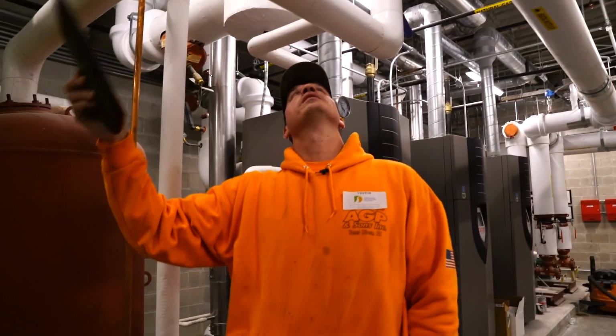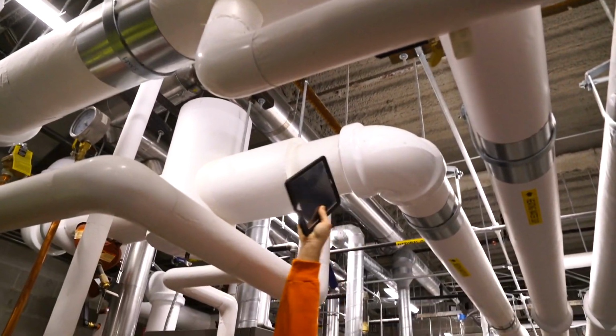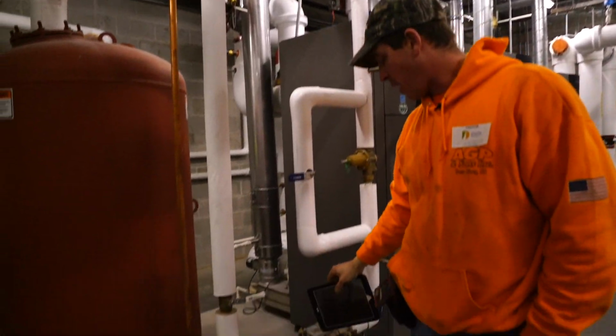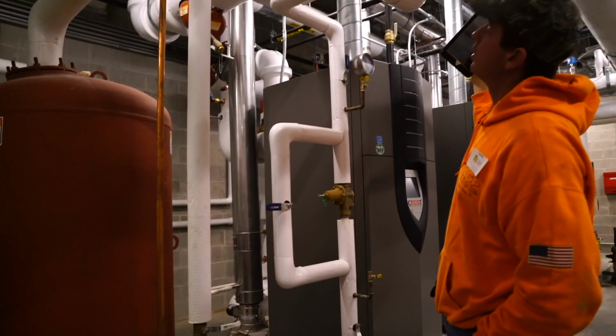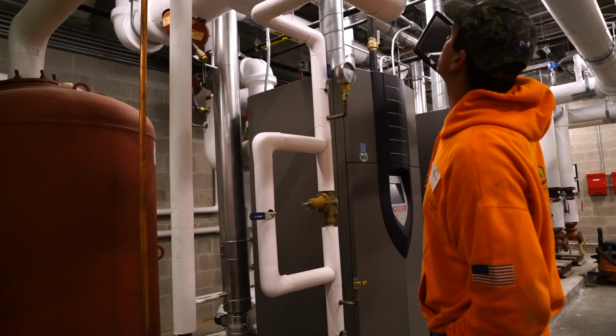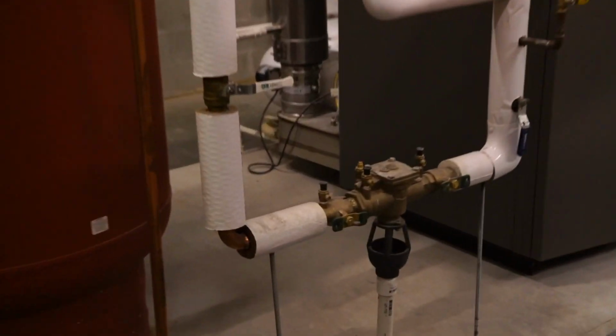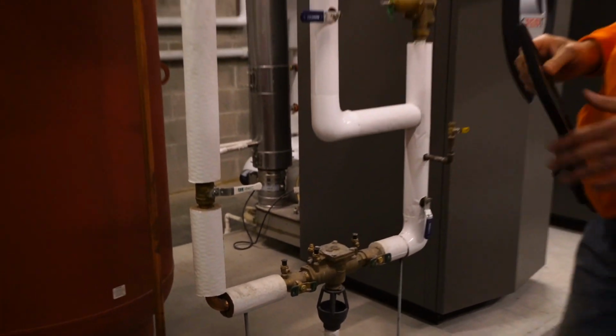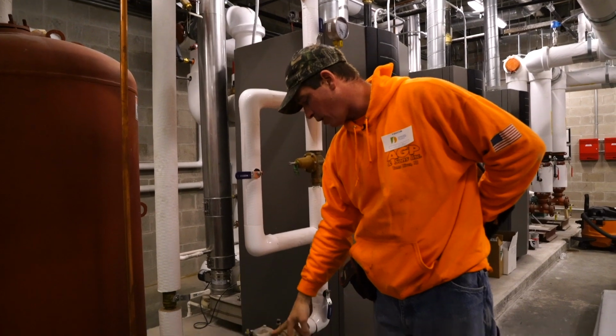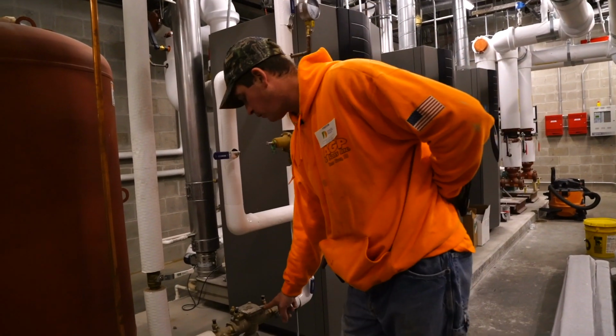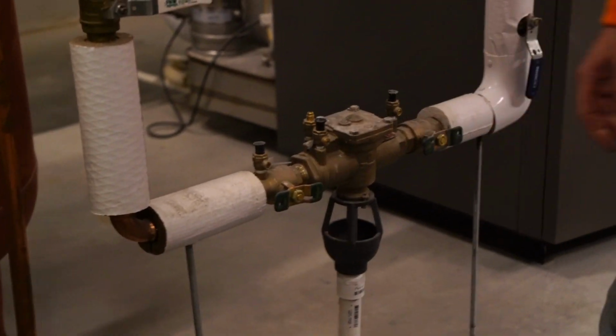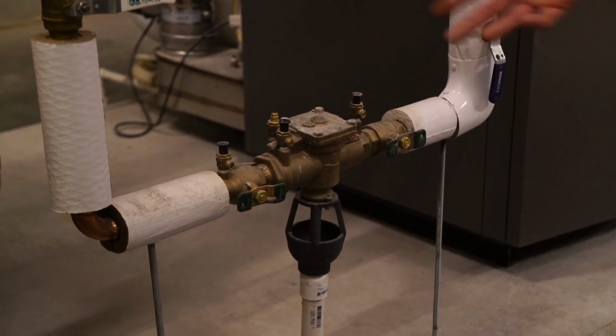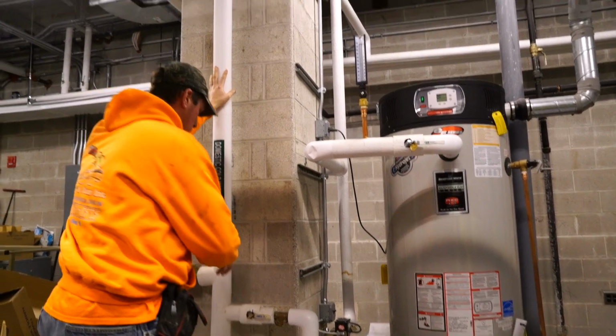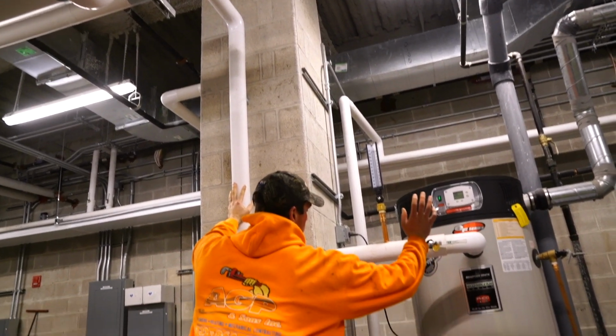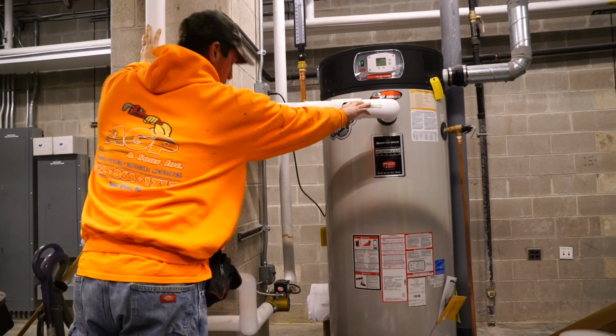The other backflow preventer we have in here comes off the domestic cold overhead. There's a line that feeds down. Another backflow feeds your HVAC system in here for your heating, supply, and return. This is the makeup water for that. They come in, they check it, they make sure it's functioning properly. Same thing, your isolation valve for that, turn it off or on. Your main cold supply going in, hot coming out, isolation valve, isolation valve.